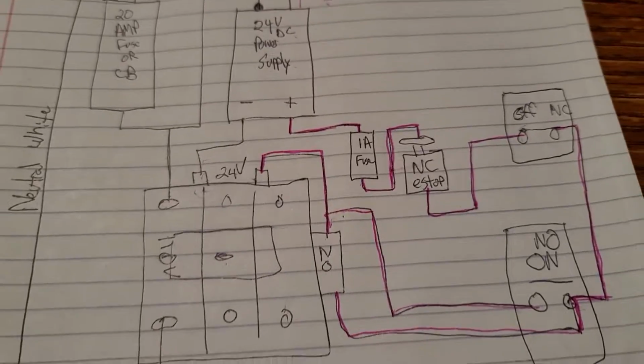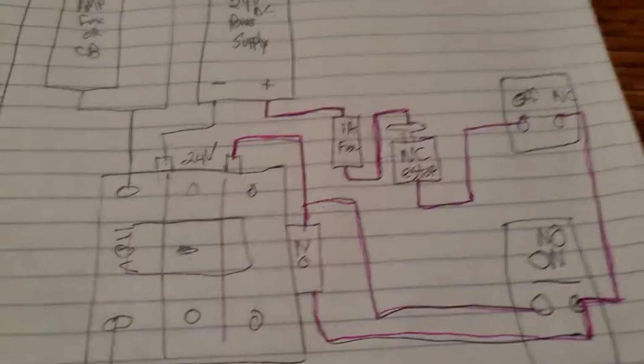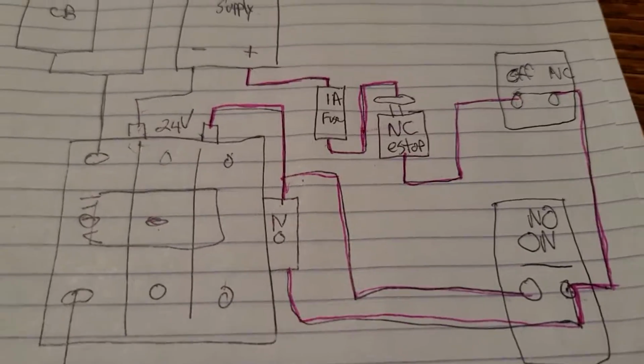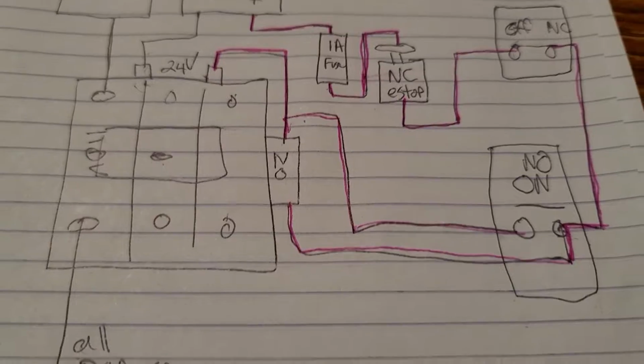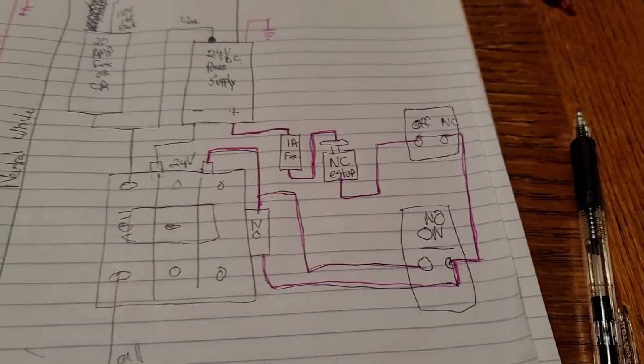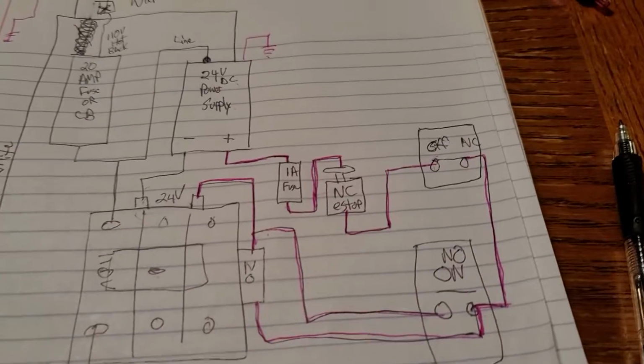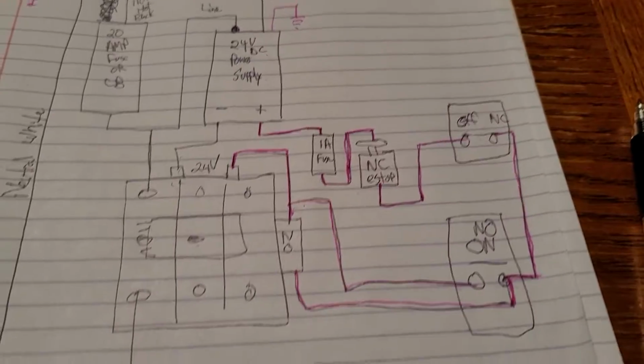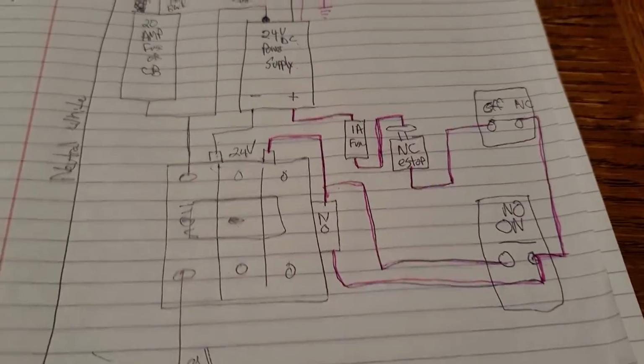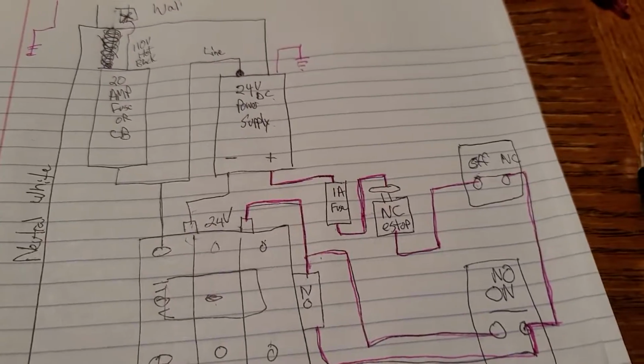And that's what you want your fingers to touch. You never want your fingers to touch buttons that have high voltages. I never design anything I build with 110 or 220 volts running through switches. You can, it's just not safe. That's why all industrial electronics always has 24 volts AC or 24 volts DC as the control voltage. Because if you get shocked, it's not going to kill you.